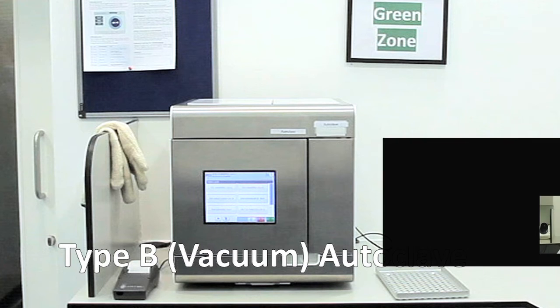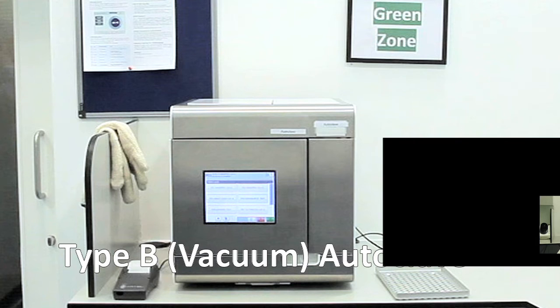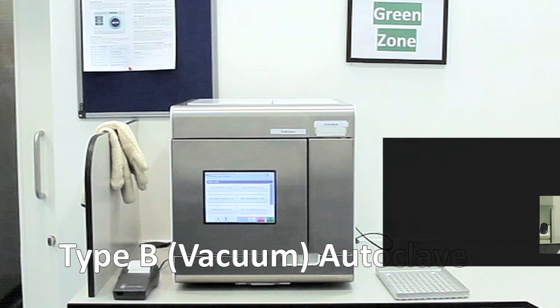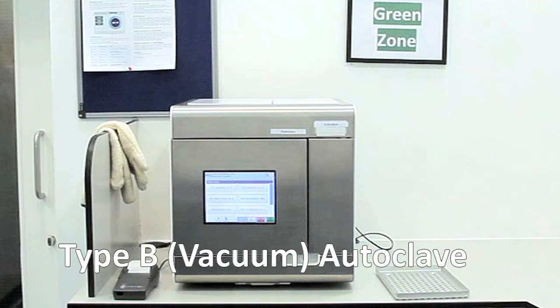RO water should be plumbed into the autoclave in order for successful sterilisation to take place. The presence of dissolved and/or suspended chemicals in water supplied to sterilisers can result in deposits on materials during the sterilisation process. If the RO water is not plumbed into the autoclave, it can be stored in easily identifiable containers. RO water should be stored in a cool area, away from sunlight and high temperatures.